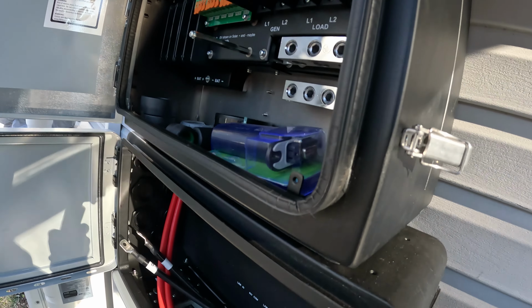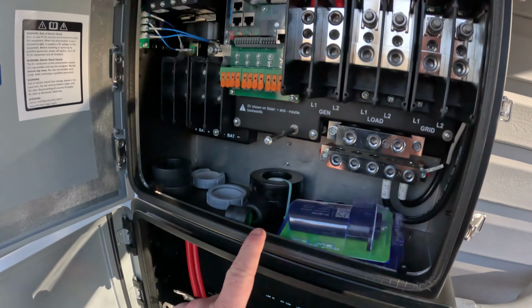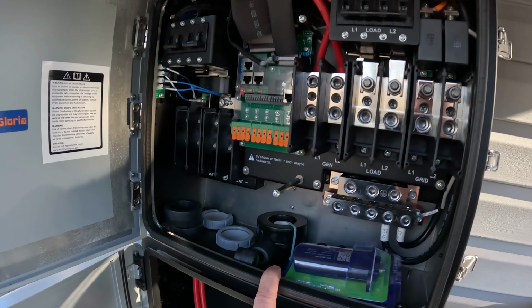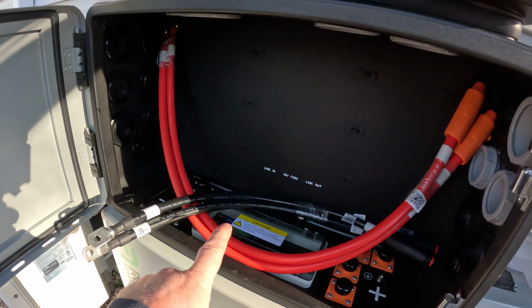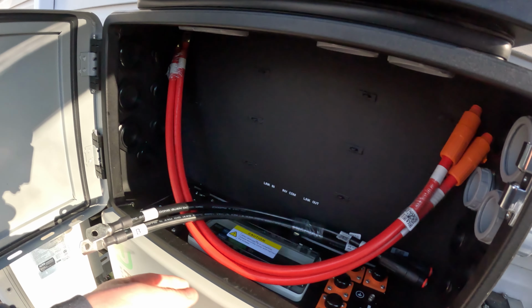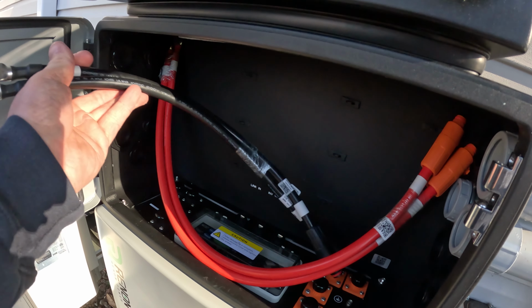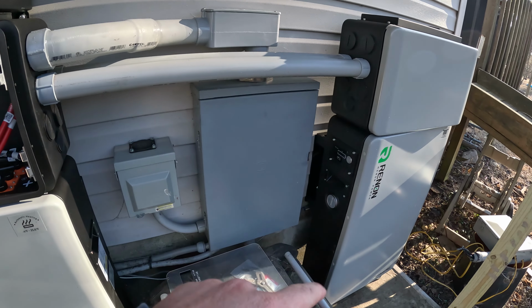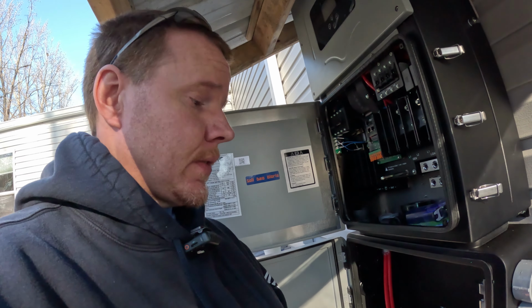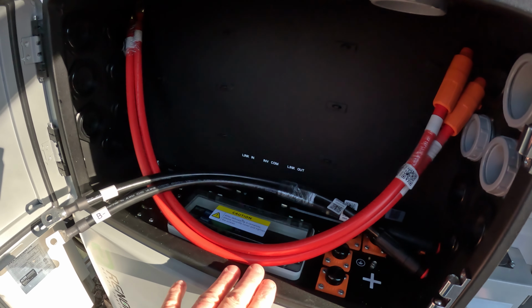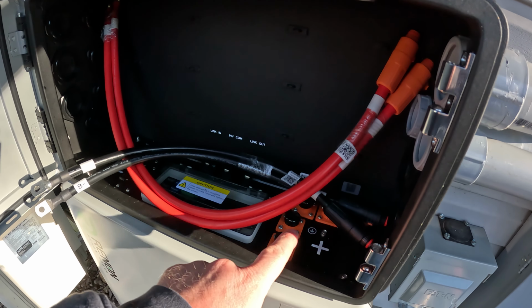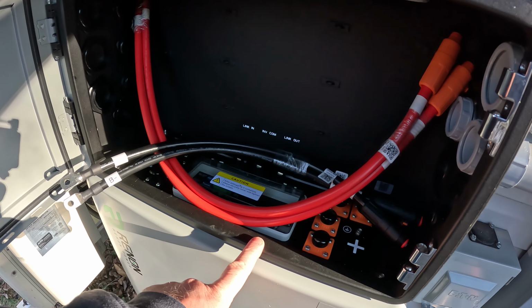We're going to go on and get battery number 1 tied in to the inverter. The battery kit came with the battery cables that feed from battery number 1 to the inverter. They're sized for this connection, and we have to make up the run between the batteries. All the batteries, as you expand the storage, connect back to each other. The only connection to the inverter is on the main battery right here. Everything else is looped back to this one. So we'll go on and get this one tied in.